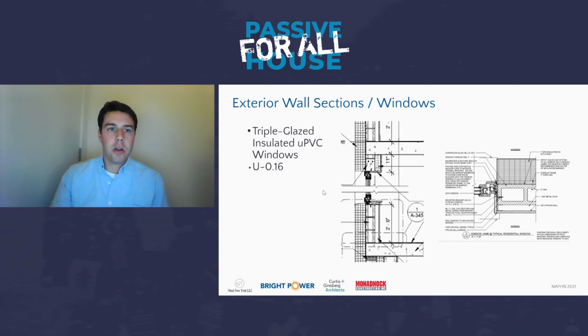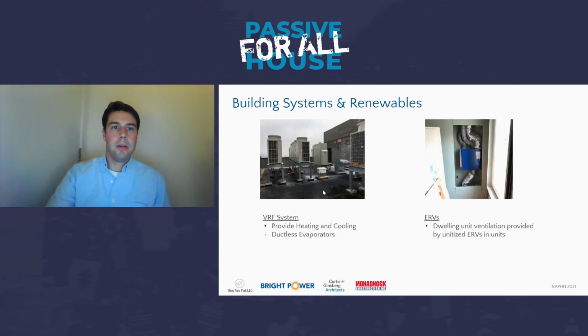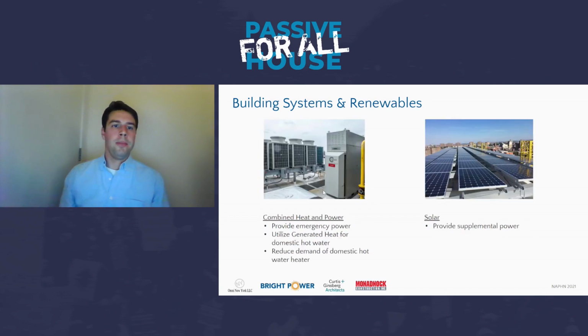Typical details of the window assemblies. The windows here are triple glazed uPVC throughout with a U value of installed 0.16. And the building systems, their VRF system for heating and cooling throughout the building with ductless indoor units. The design team reviewed early on centralized versus decentralized ERVs and decided to have decentralized unitized ventilation ERVs throughout in each dwelling unit. You can see an image here during construction.